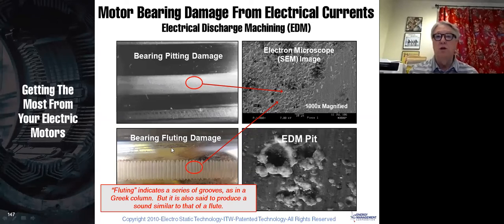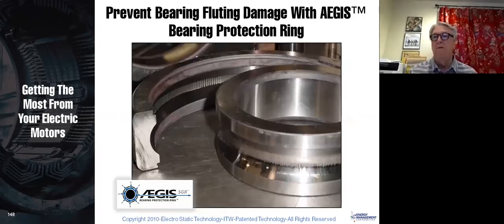As it gets worse, it turns into bearing fluting damage. So you can see over here, this looks like the fluting. You've seen fluted columns on Greek temples and a lot of architecture. That's where they get that name from. And once it gets here, your bearing is just going to sing. It's going to get really loud. You're going to see the vibration pick up, and you are then on the verge of a bearing failure.